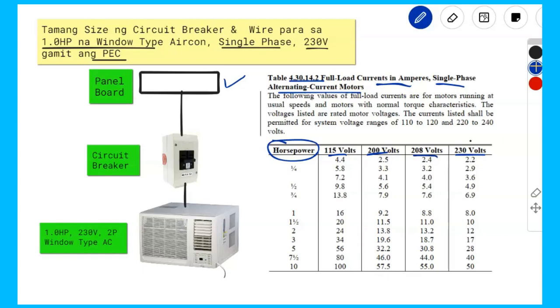So, itong ating aircon is 1 HP. So, dito tayo sa row na ito. Tingnan natin. Itong 1 HP na aircon, if i-check mo yung voltage, that is 230. So, dito ka sa column na ito. Okay, if tingnan mo yung full load ampere niya, that full load current is 8.0. So, ang gagamitin nating amperahe is 8.0 amperes. So, let's use that to determine kung anong size ng wire na magagamit natin.